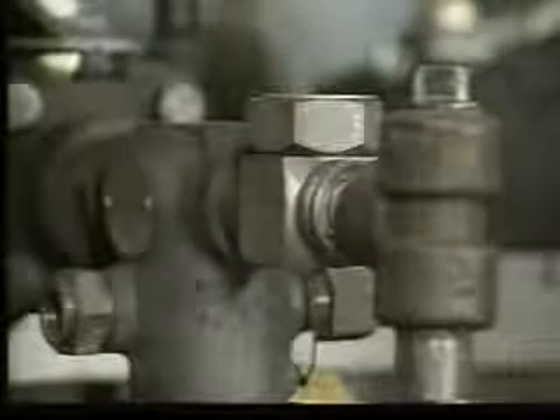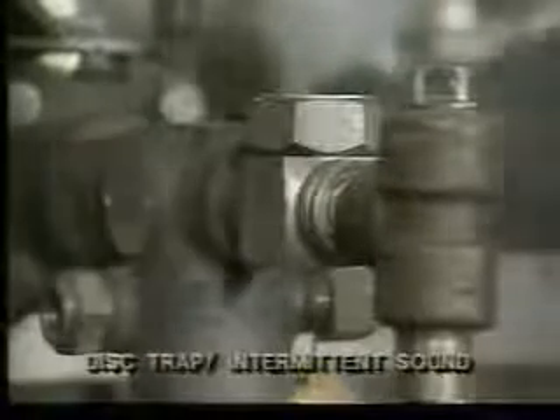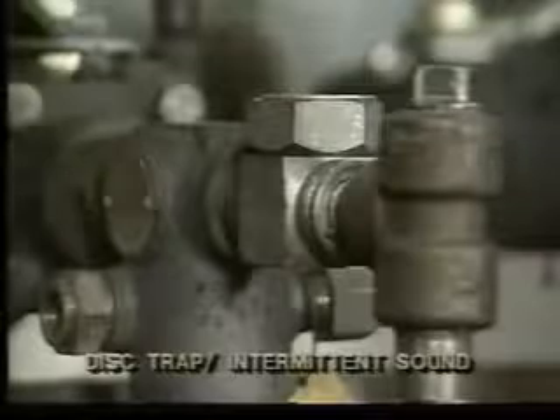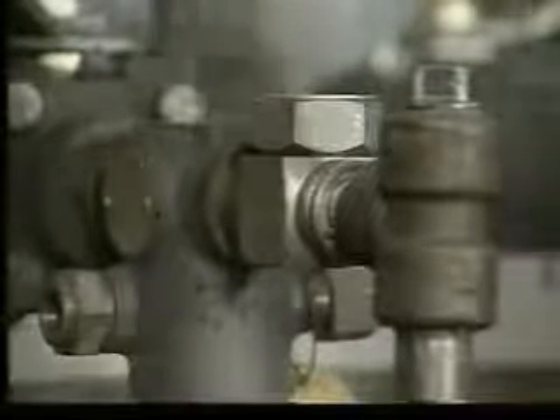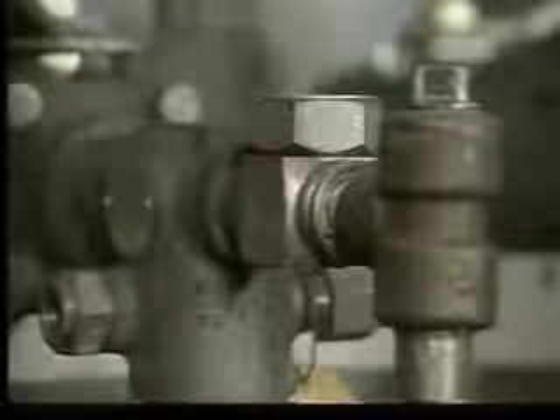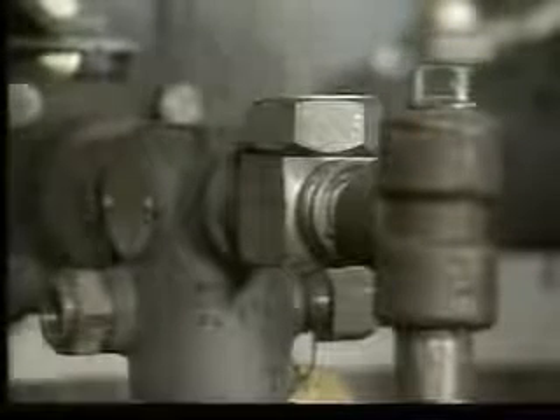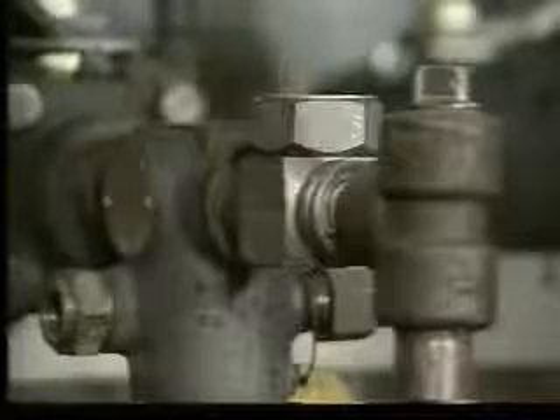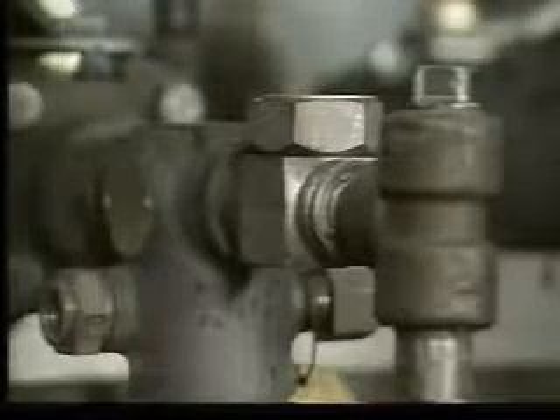The disc trap is an intermittent trap with a distinctive sound pattern of opening and closing. If rapid cycling occurs, the trap will fail open and waste live steam. This failure, or blow-through, has a loud, high-pitched sound.